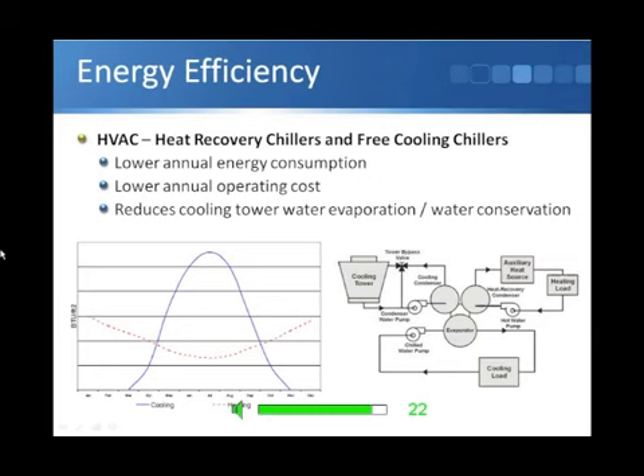Free cooling chillers are where we would run the cooling chilled water system through the chiller itself and through the cooling towers, but we might not operate the refrigeration system, and we might be able to operate on chilled water that's allowed to float up to higher temperatures, maybe 10, 11, 12 degrees C, instead of trying to operate at 6 degrees C all the time. And that would have a significant energy benefit. And the point about those systems, of course, is that that plant is there and able to run when we do get to our peak cooling days and we do need chilled water at 6 degrees C. It's really just a situation where we're able to drop back and use free cooling when we can.